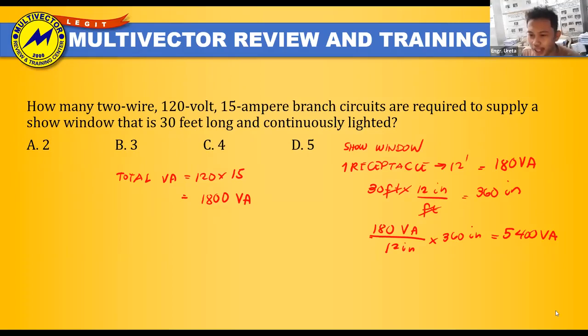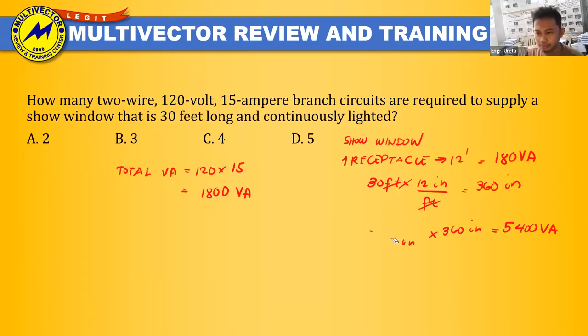Okay, so 5,400 volt ampere. So 1,800. Per receptacle, meron daw tayong 180 volt ampere. Ilang receptacle ba yung kailangan natin? Yung total volt ampere natin, i-multiply lang natin ng 1.25.